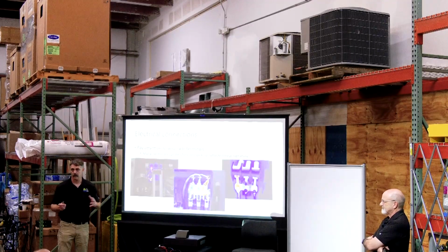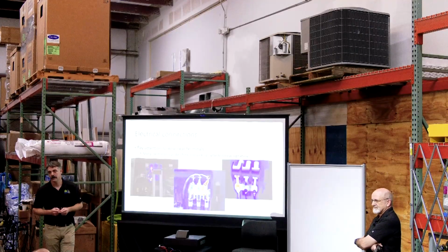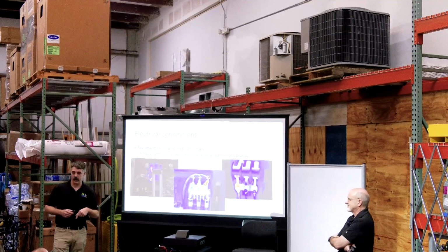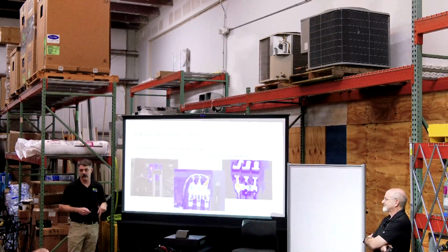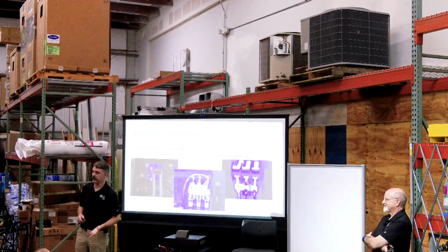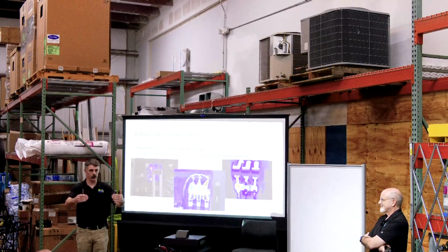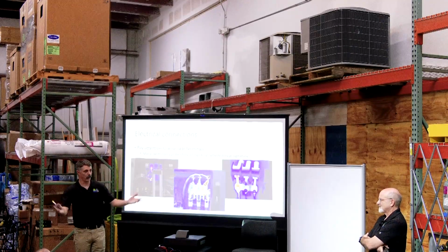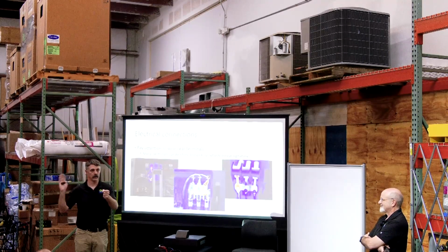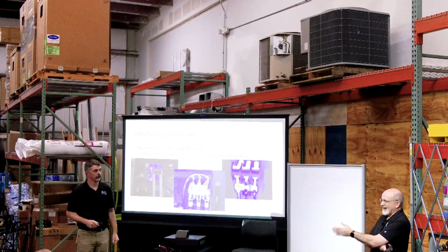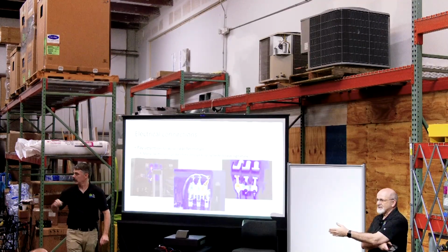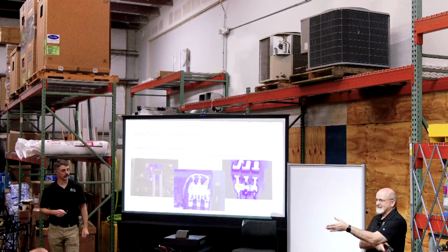Yeah. So you can also be the heat source that's being reflected. That is correct. Absolutely. If you play with a thermal camera, one of the first things that you should play with is walk up to a plate glass door, you know, sliding glass door, big window, whatever you want to do, and wave at yourself in the image because you'll get to see yourself. Because glass is a thermal mirror. You know, silver mirrors are visual mirrors to us. Glass is a thermal mirror.